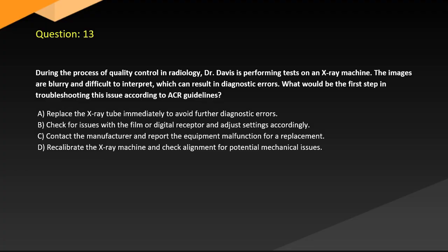Question 13. During the process of quality control in radiology, Dr. Davis is performing tests on an X-ray machine. The images are blurry and difficult to interpret, which can result in diagnostic errors. What would be the first step in troubleshooting this issue according to ACR guidelines? A. Replace the X-ray tube immediately to avoid further diagnostic errors. B. Check for issues with the film or digital receptor and adjust settings accordingly. C. Contact the manufacturer and report the equipment malfunction for a replacement. D. Recalibrate the X-ray machine and check alignment for potential mechanical issues.